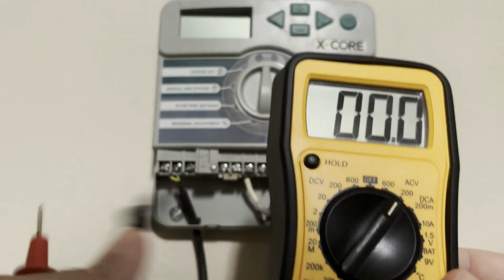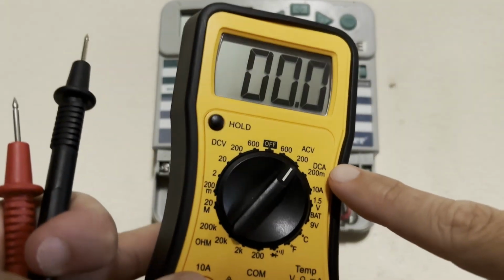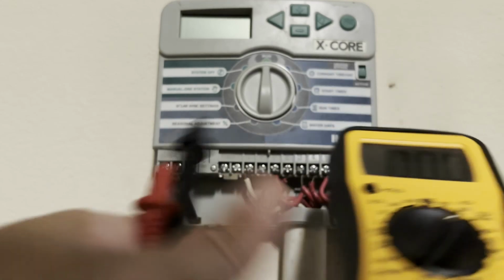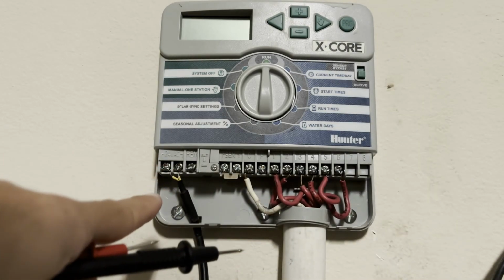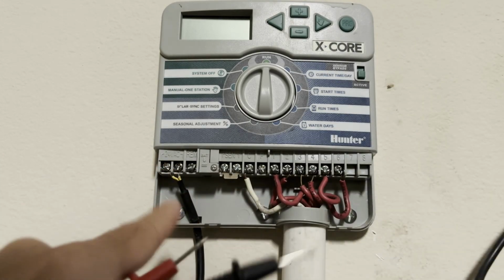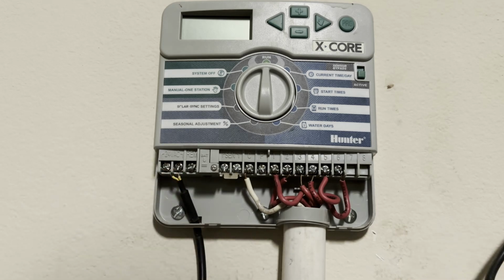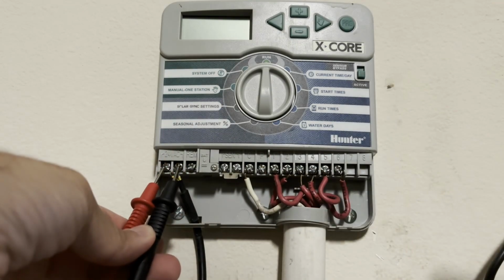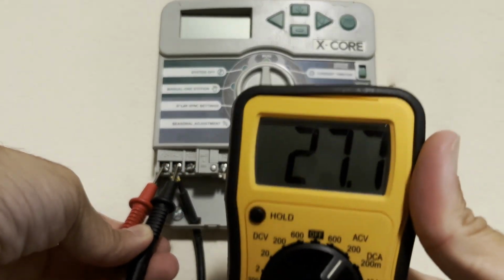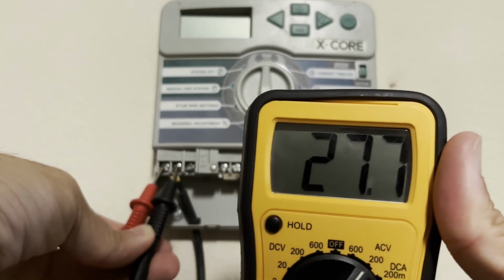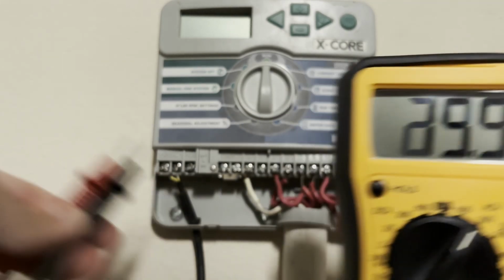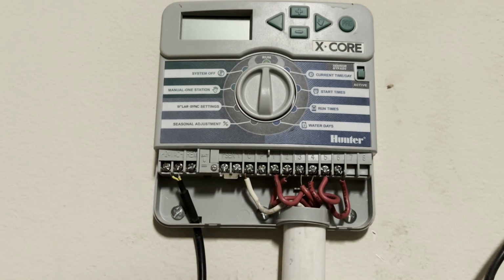Next, grab a multimeter set to read AC volts and touch the two inputs coming off the power transformer. You should get a reading between 24 and 28 volts if you're getting power into the unit. Here you can see I've got 27 volts, which indicates I am getting power from my transformer into my control panel.